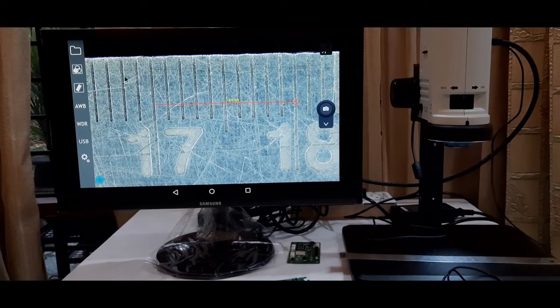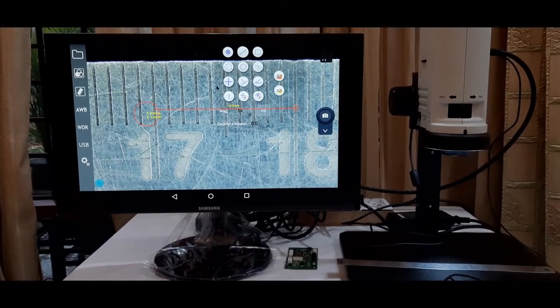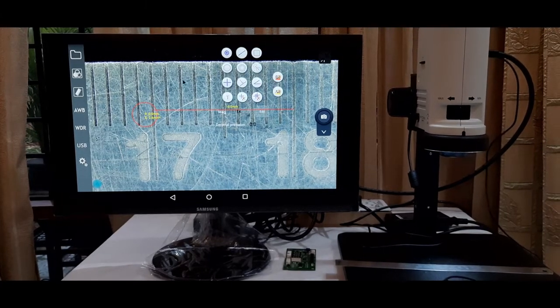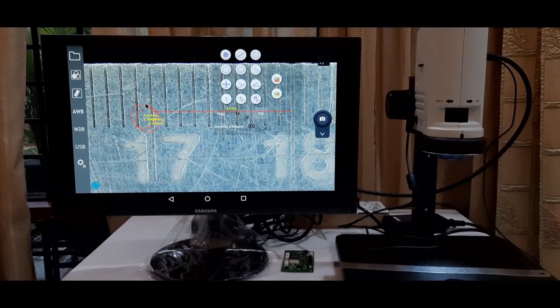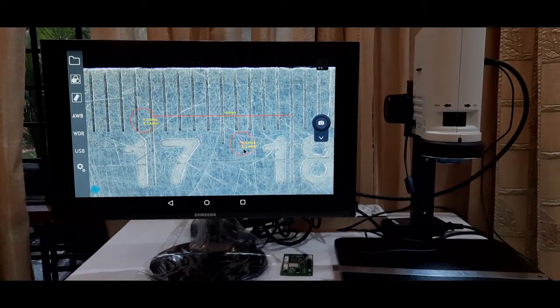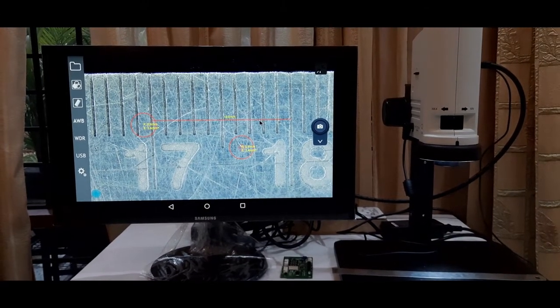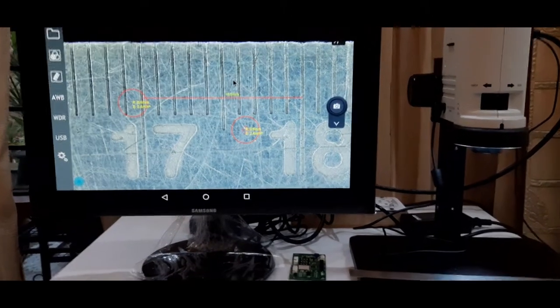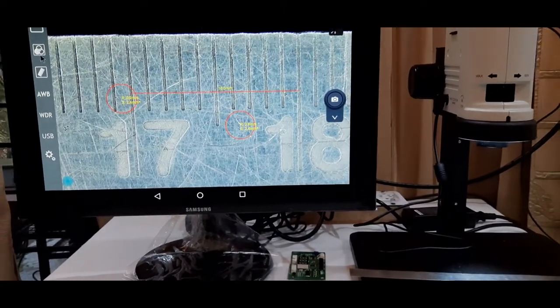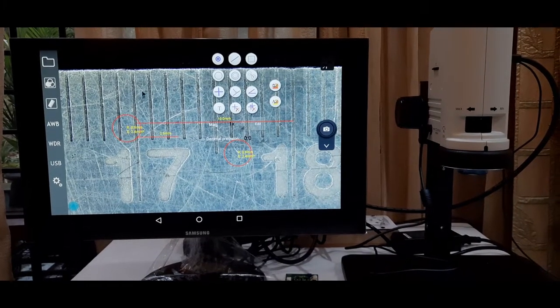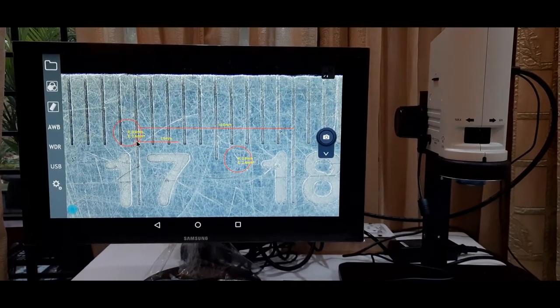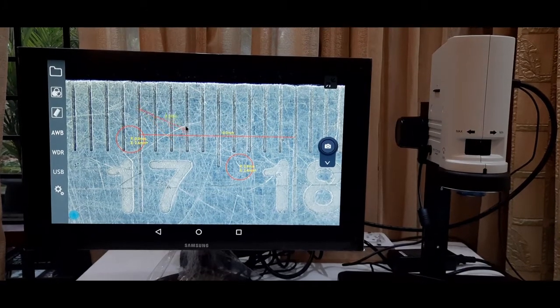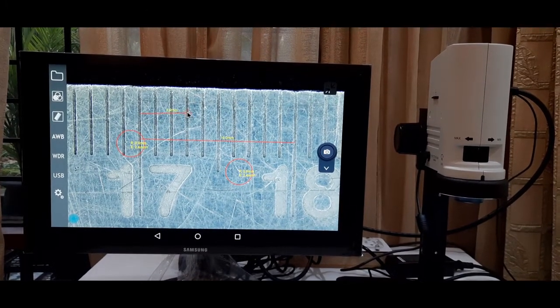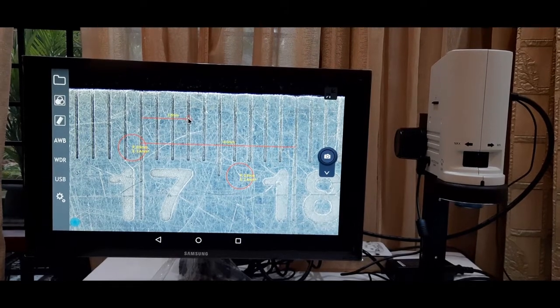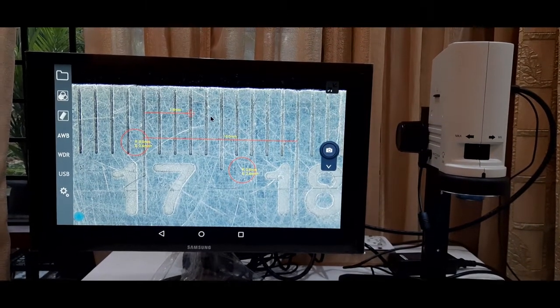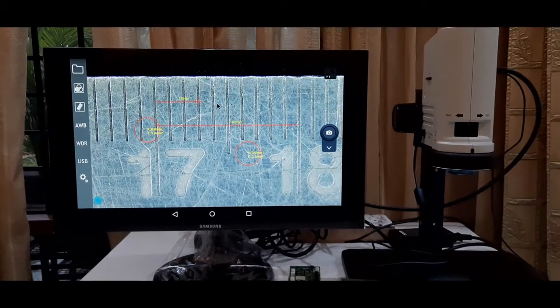So now we can select the circle or any other geometrical figure, and the calibration performed by us will give us the accurate value. Suppose we need to measure one more line, this line, this is 3 mm, and the actual value, the magnified value on the magnified image, is also 3 mm. So this is how we can make use of this calibration feature.